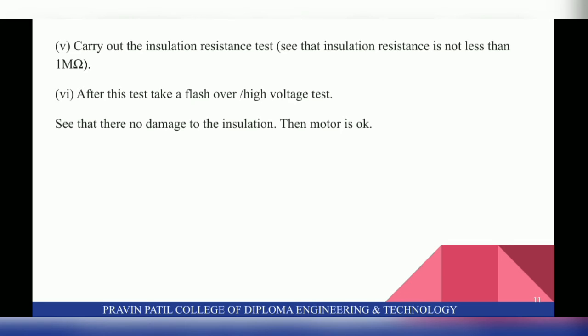Carry out the insulation resistance test, see that insulation resistance is not less than 1 mega ohm. After these tests, take a flashover or high voltage test, see that there is no damage to the insulation, then motor is okay.